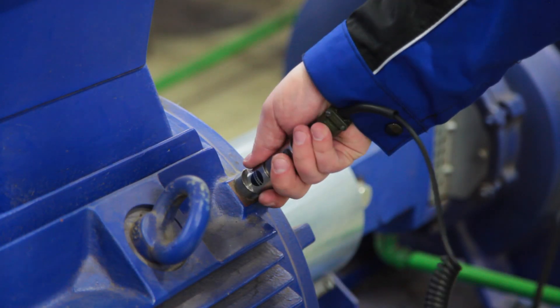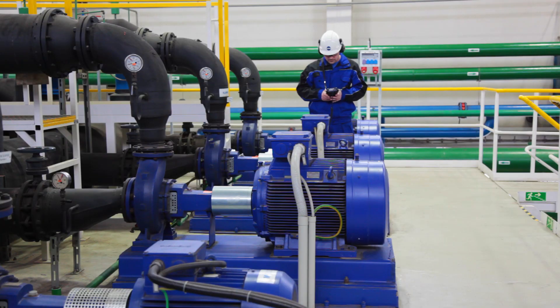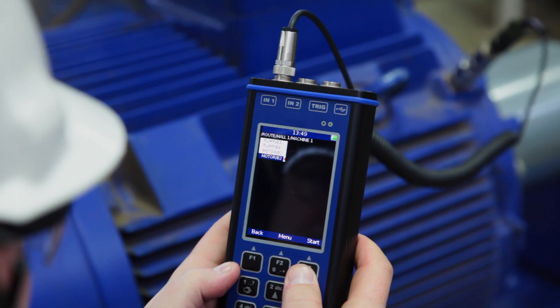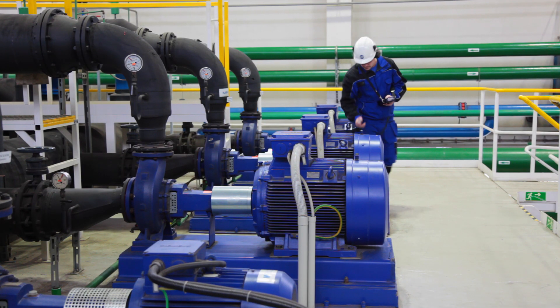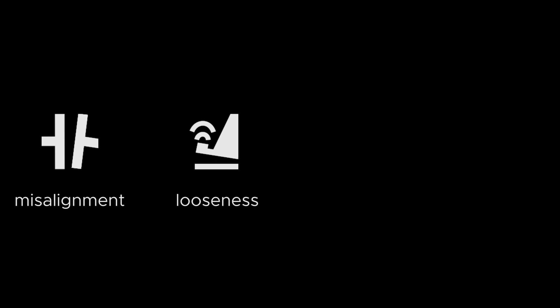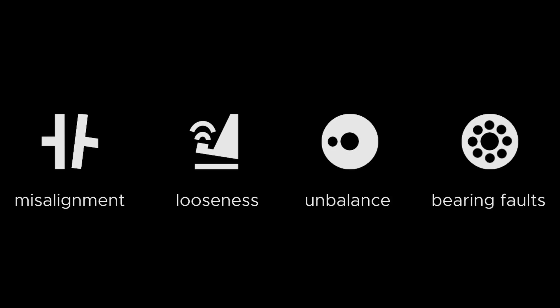All mechanical and some electrical motor faults have a unique signature in the vibration spectrum of the machine and vibration analysis can recognize them. Failures such as misalignment, looseness, unbalance and bearing faults are diagnosed according to the same rules applicable for all other machinery parts.